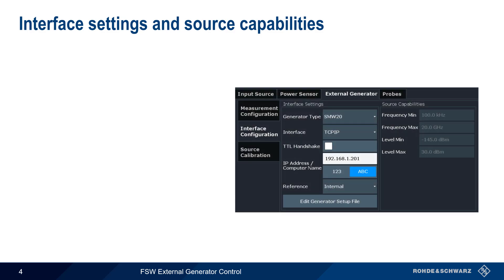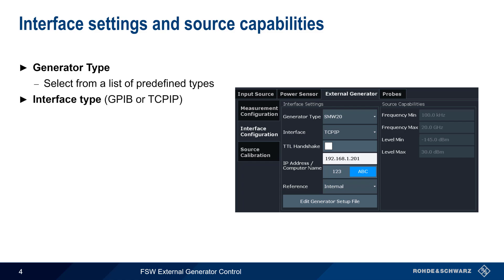We'll start with Interface Configuration. Here we select the type or model of generator from a list of predefined types. We also need to choose the interface used to connect the FSW to the generator. This can be either GPIB or TCPIP — that is, an Ethernet or LAN connection. The GPIB address, or the IP address/hostname, must also be entered.